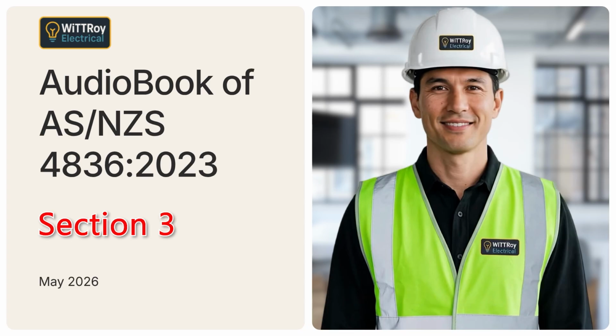The key message is simple. Isolating the item you are working on may not be enough. If there are live parts nearby, those live parts must also be considered and controlled. A worker must not be placed in a position where accidental contact with nearby live parts can occur.